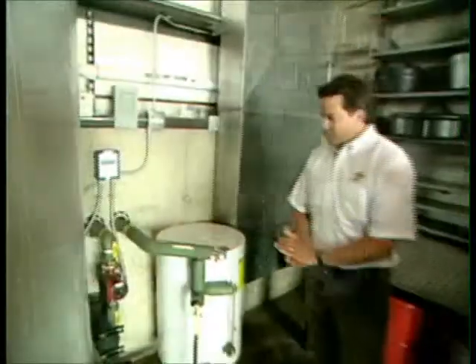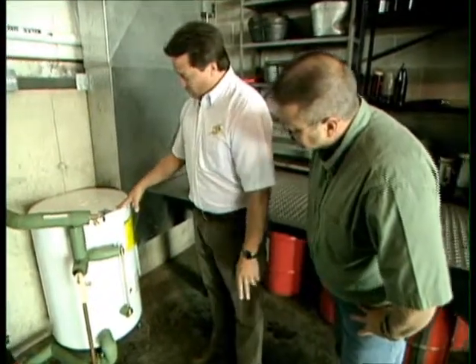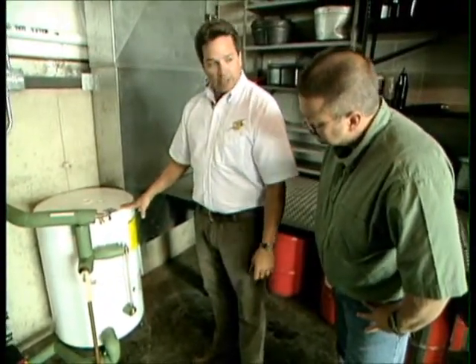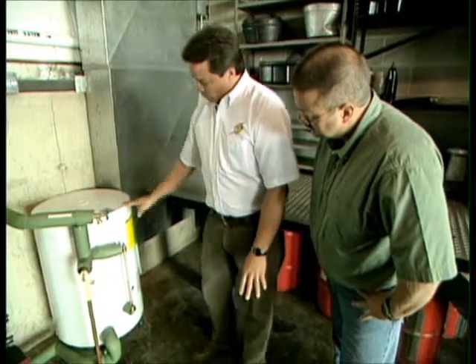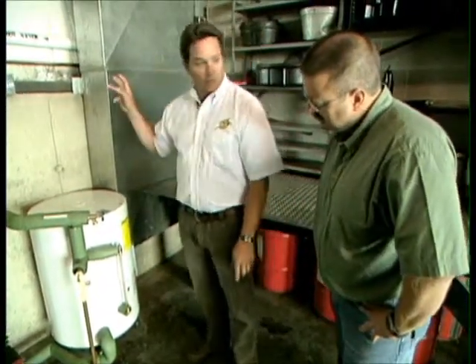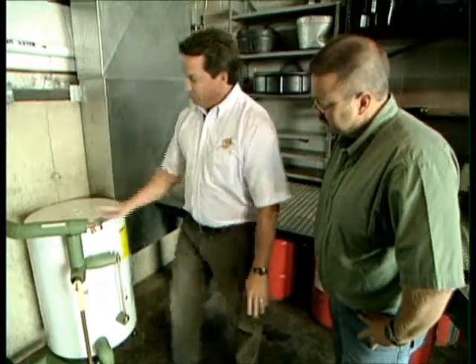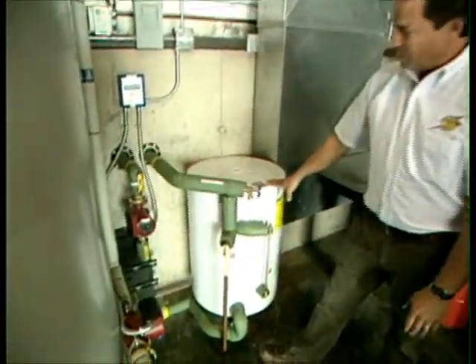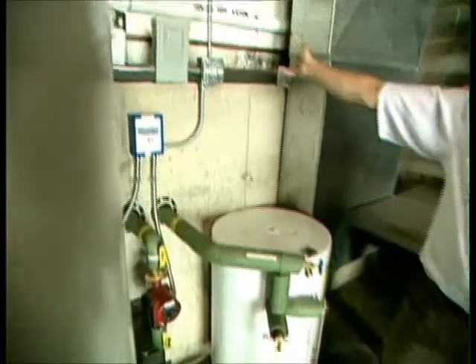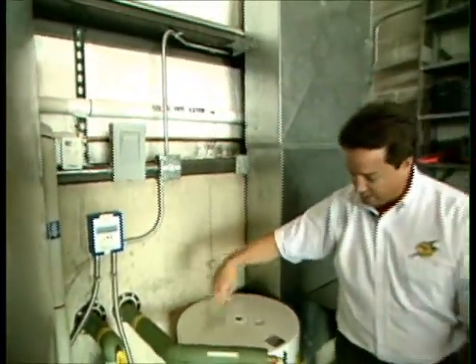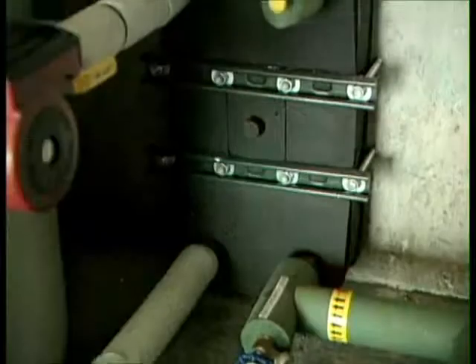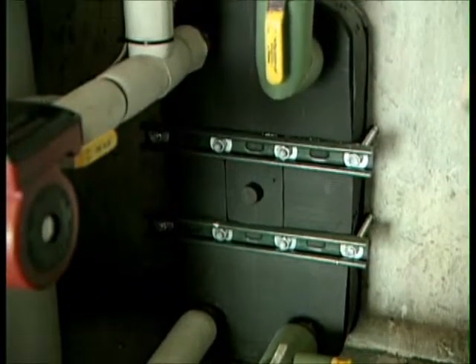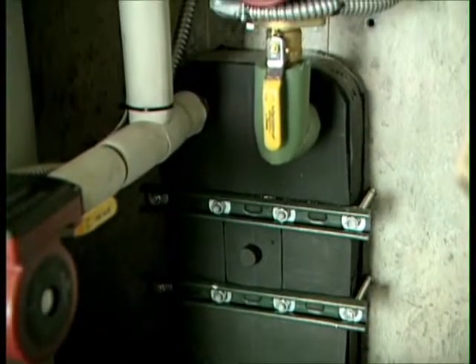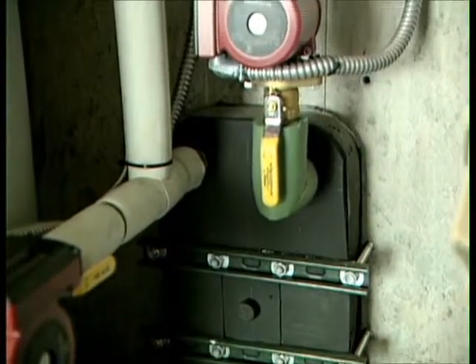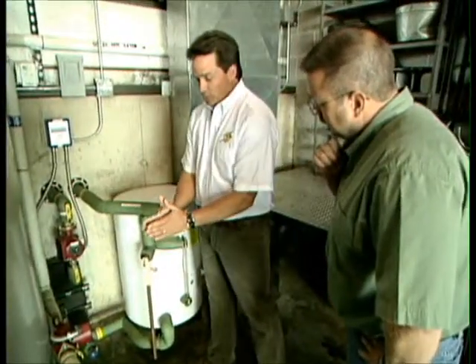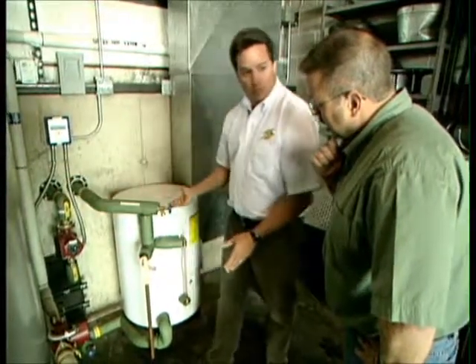Well, Stu, here we are inside the facility now, and this is the glycol storage tank, or drainback tank as it were. This holds the solar fluid until the system calls when the heat's available. The pump then turns on and takes the fluid out of this tank and sends it up to the collectors to gather the heat energy. The fluid then comes back through this heat exchanger and transfers that heat to the domestic water, which is in here. Now, how does the heat exchanger actually operate? This is a plate and frame heat exchanger. It's a double wall heat exchanger to protect the domestic water supply from the propylene glycol.